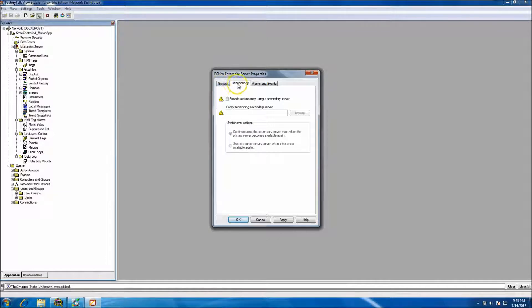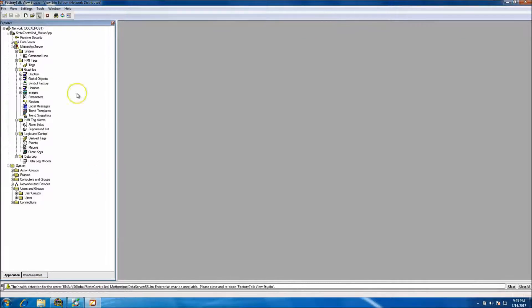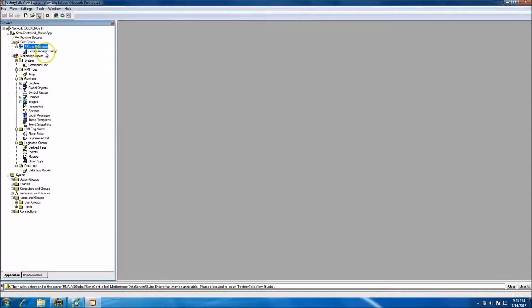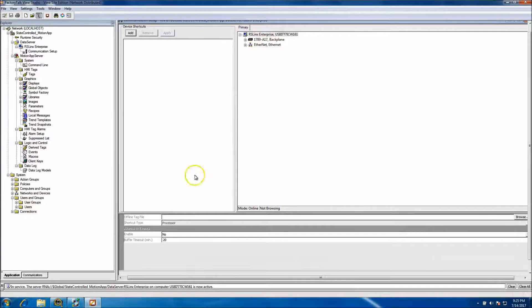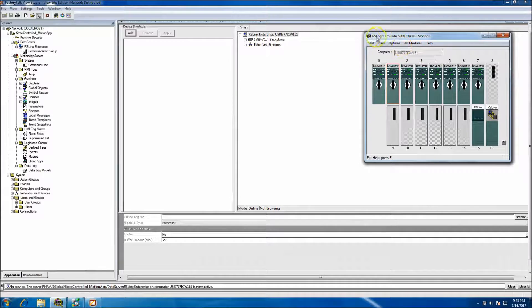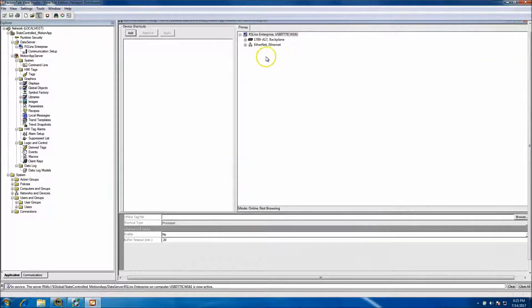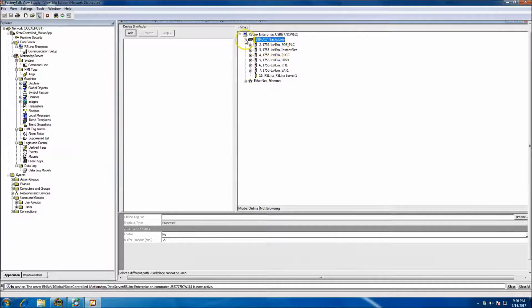We're not using redundancy; we'll go ahead and set up our enterprise and hit Apply. This sets up our RSLinx. For the RSLinx path, we're going to use the emulator processor — the RS Logix Emulate 5000 chassis through the 1789 backplane. It shows we don't currently have it loaded, so we won't add anything right now.